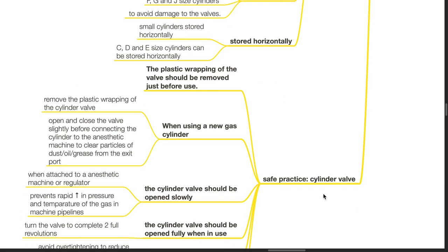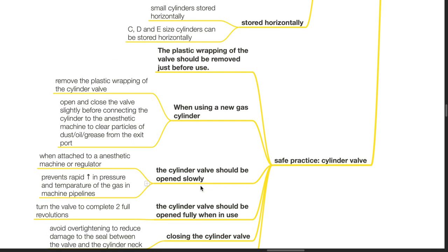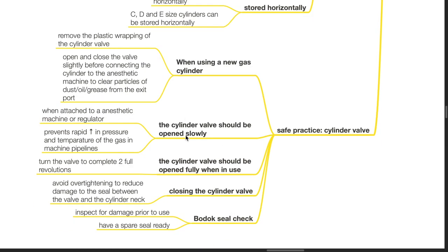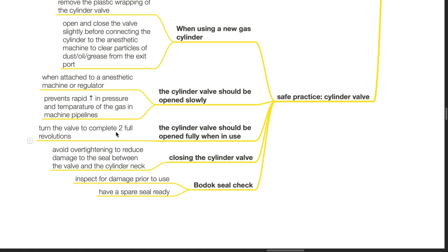Safe practice cylinder valve: The plastic wrapping of the valve should be removed just before use. When using a new gas cylinder, remove the plastic wrapping, open and close the valve slightly before connecting the cylinder to the anesthetic machine to clear particles of dust, oil, grease from the exit port. The cylinder valve should be opened slowly when attached to the anesthetic machine or regulator. This prevents rapid increase in pressure and temperature of the gas in the machine pipelines. The cylinder valve should be opened fully when in use. Turn the valve to complete two full revolutions. Closing the cylinder valve: Avoid over tightening to reduce damage to the seal between the valve and the cylinder neck. Bodok seal check: Inspect for damage prior to use and have a spare seal ready.